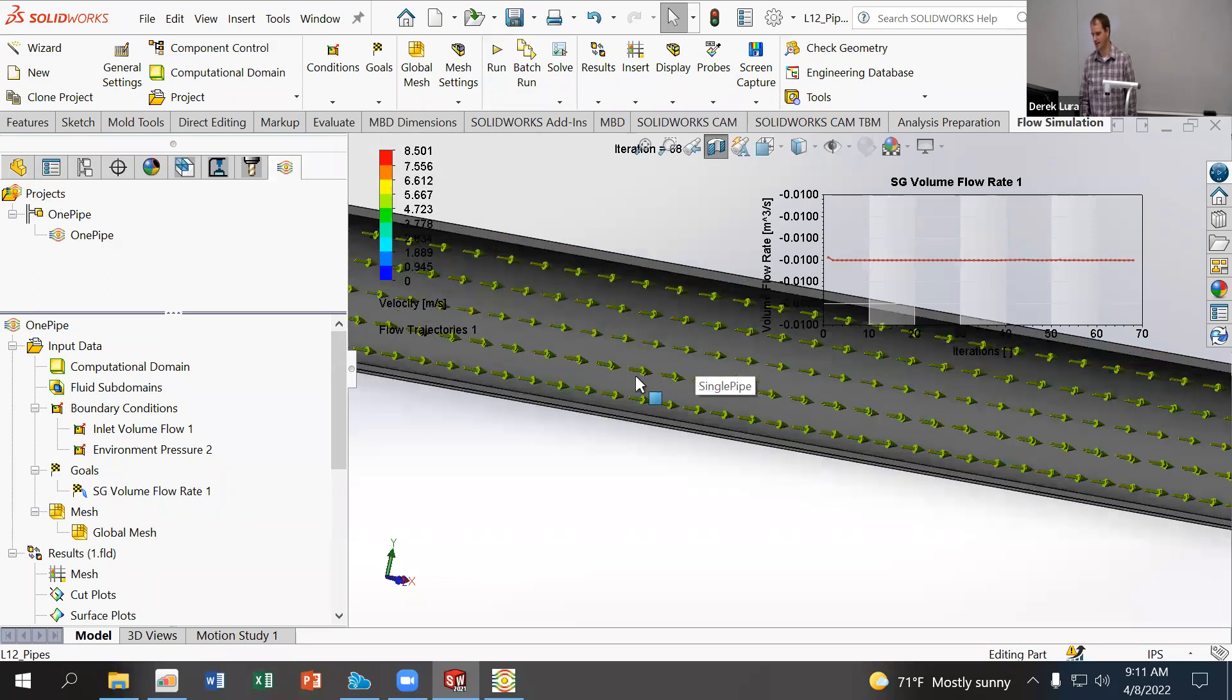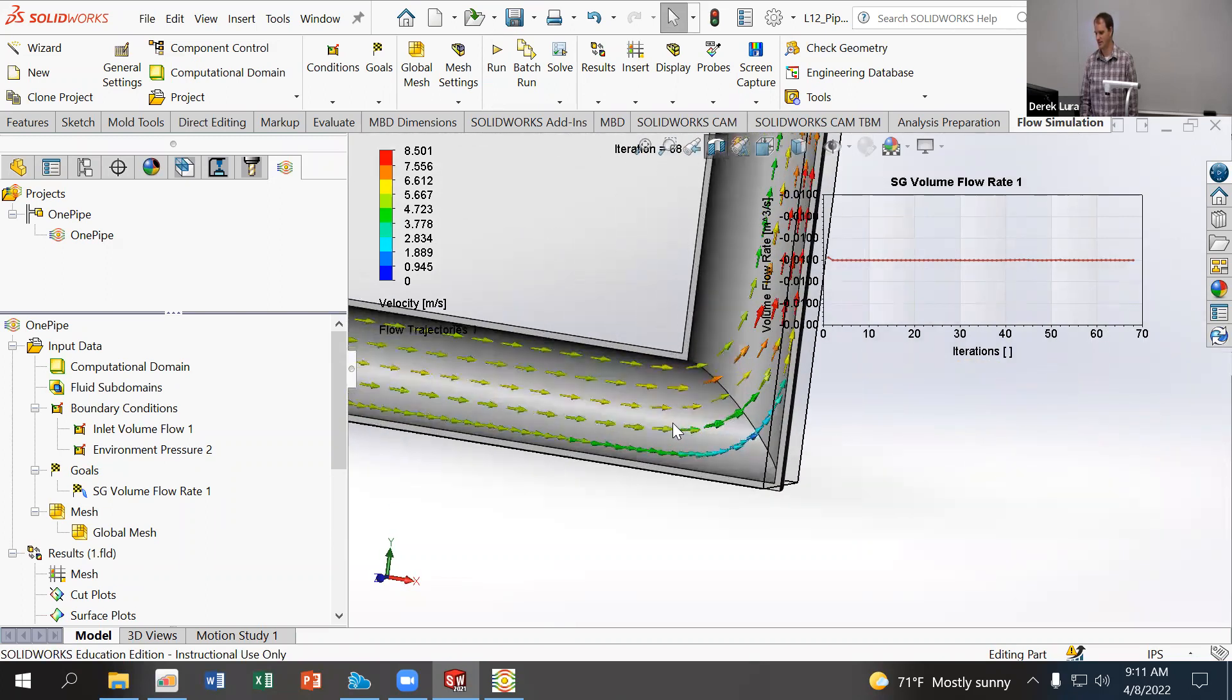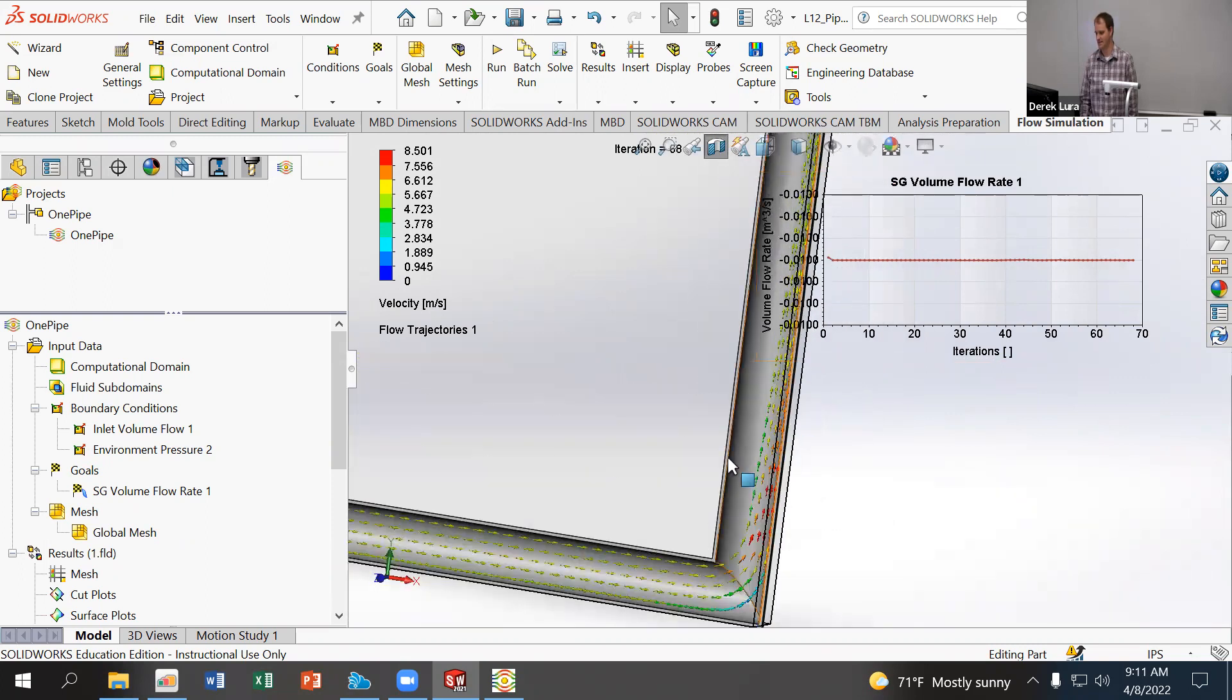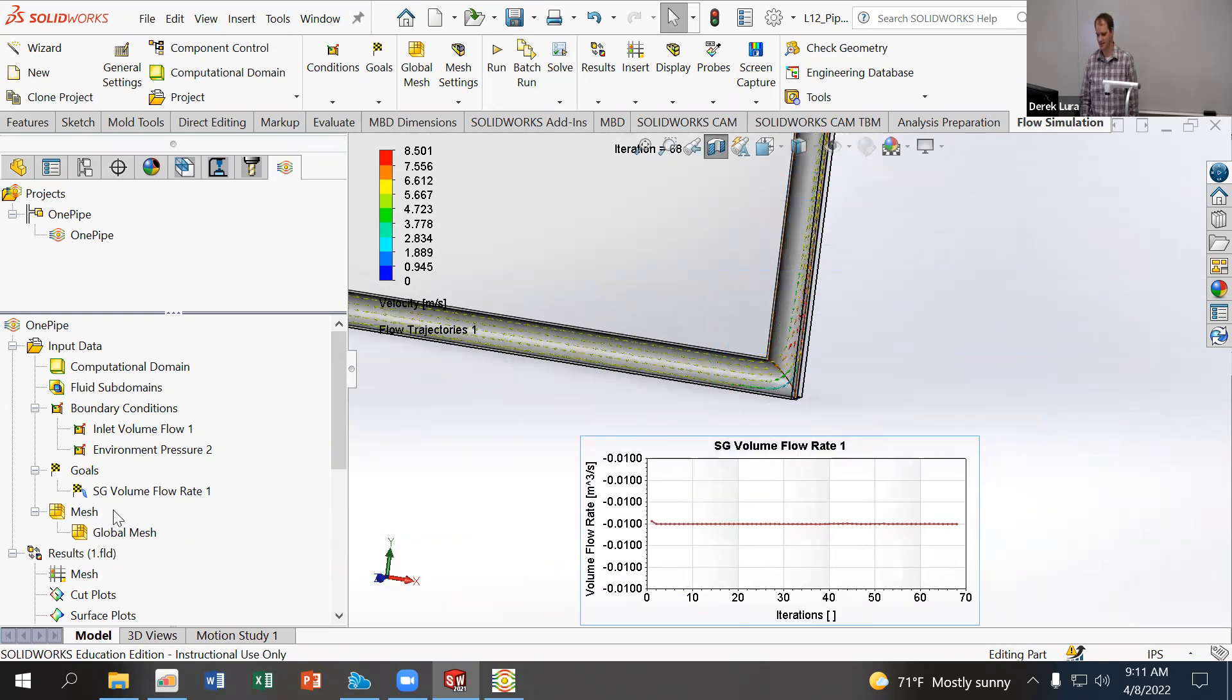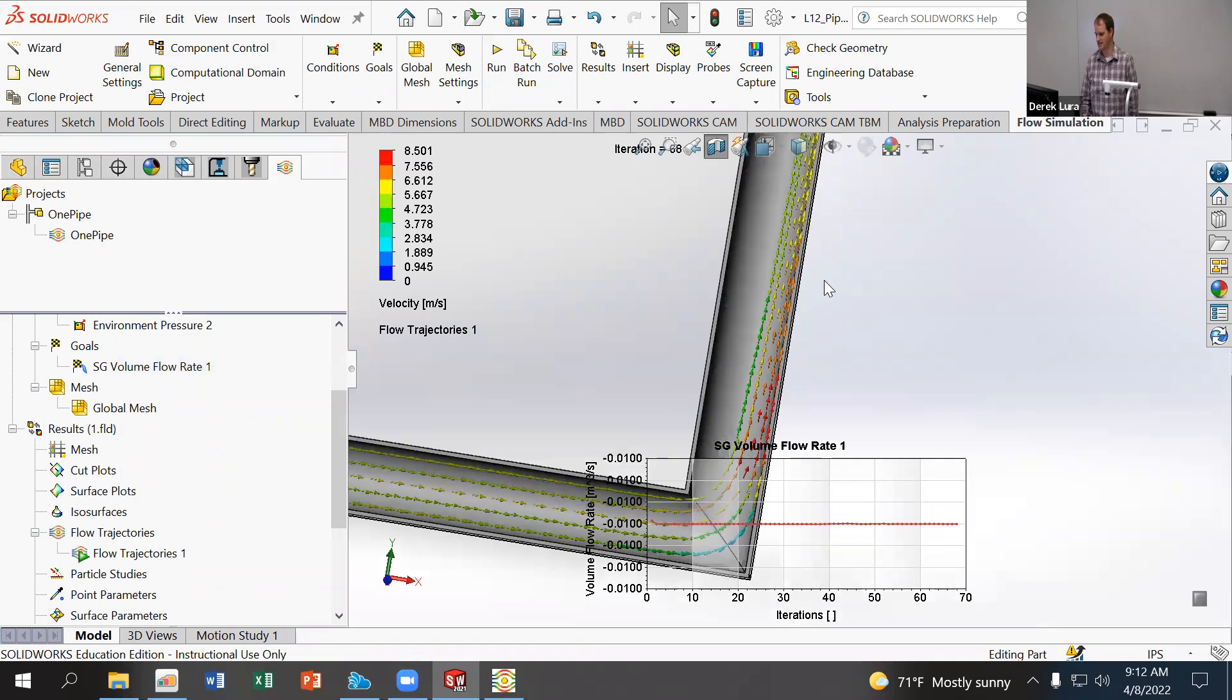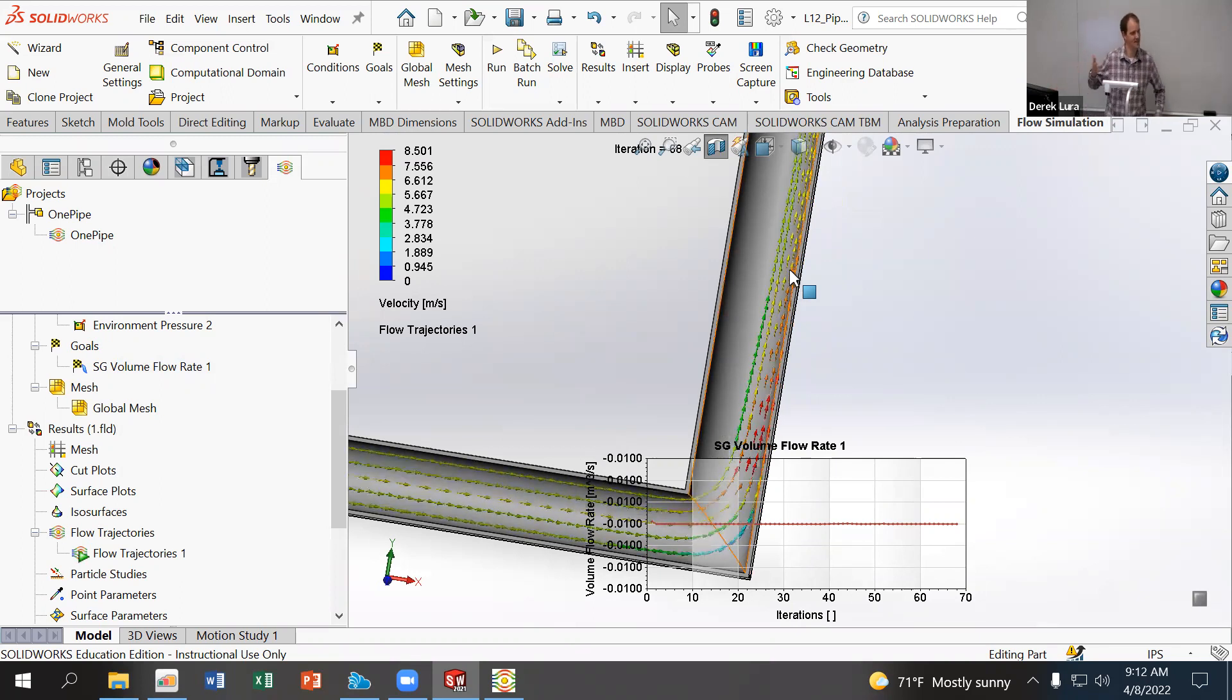So you see like the velocity coming in the inlet, pretty constant. It's actually a little bit faster in the middle than it is on the outside, but this is a big pipe. Then we get to the outlet. There's a little bit of a choke here. The velocity has to turn that corner, so it really squishes up against that far wall and speeds up. And then because it is no longer evenly distributed, it's obviously much lower at the wall than it is there. And one of the other things that's cool about this is I can animate these. So if you right-click on your flow trajectories, you can hit play, and it shows you like a little visualization of the flow.